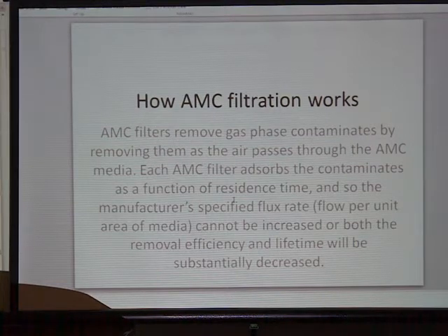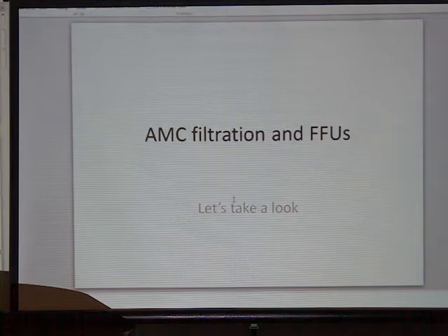So it's very important in the application of these filters that they're not run at too high a flow rate. Flow rate being higher than the manufacturer's specification, which is typically 100 feet per minute, similar to air filters. And if you increase the flux rate, the flow rate per unit area through the media, it will become less effective because it doesn't have the residence time to do the job that it's supposed to do. And you'll see why that's important as we get into this.